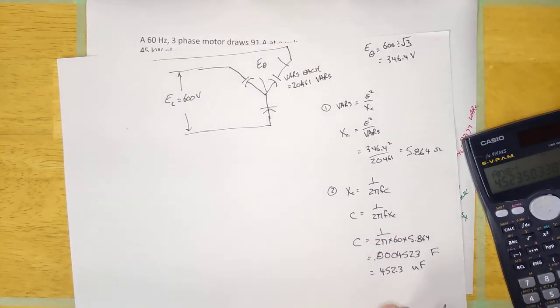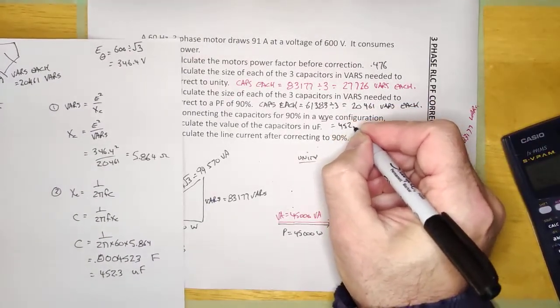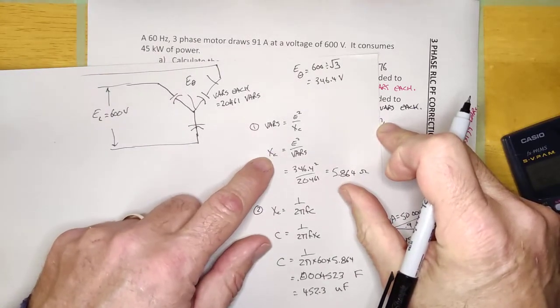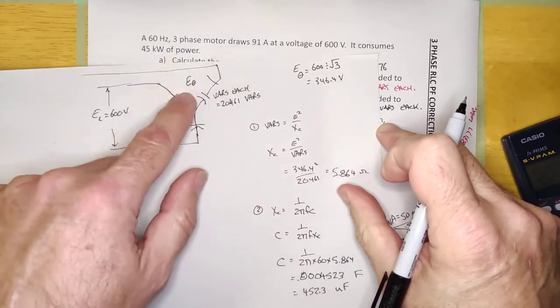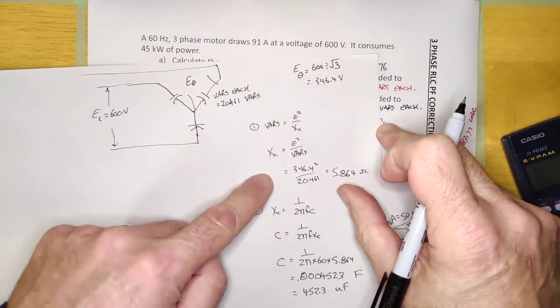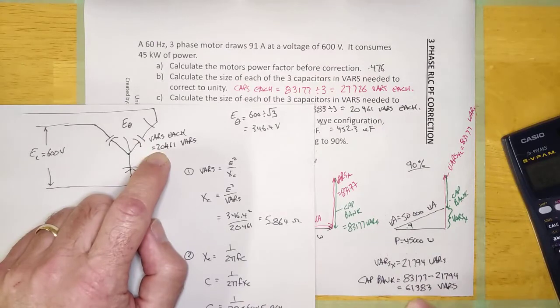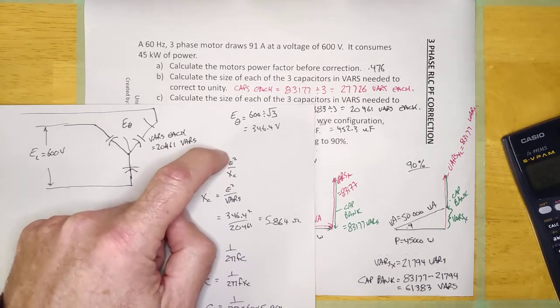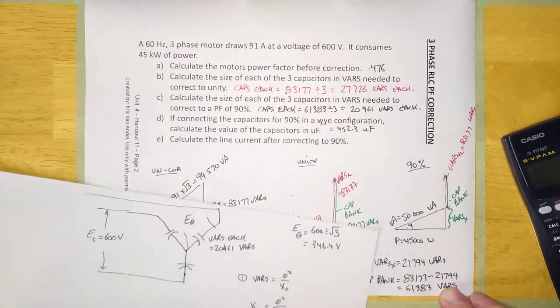And that is the answer. All that work for this one, 452.3 microfarads. What did we do there? Same as single phase. We figured out how many ohms it was, but we need to be careful to use the phase value of voltage. And since it was Y, I had to calculate it using divide by root 3. Step 2 was the same as single phase. Also, you must use the value of the capacitors each in here because there's also the whole bank. That's not going to work. So, you need the voltage dropping across the thing divided by the VARs of the thing, not the whole bank.